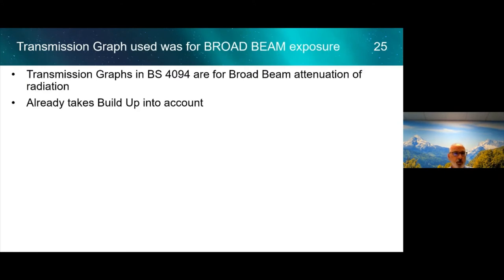The transmission graph that we used was for what we call broad beam exposure. And all the transmission graphs in the standard are for broad beam exposure. What that means is that these graphs of the transmission of radiation already take build-up into account.